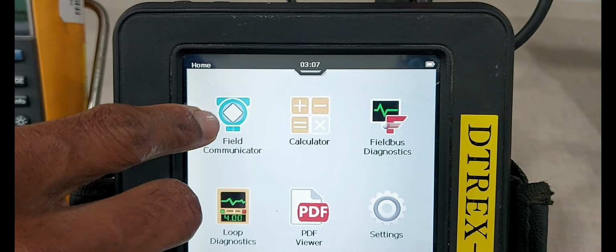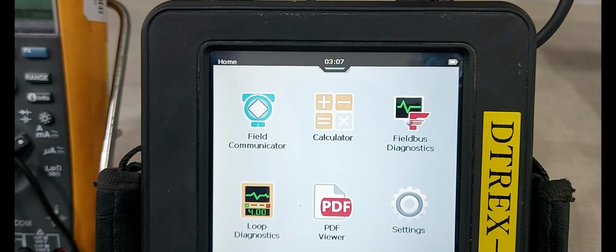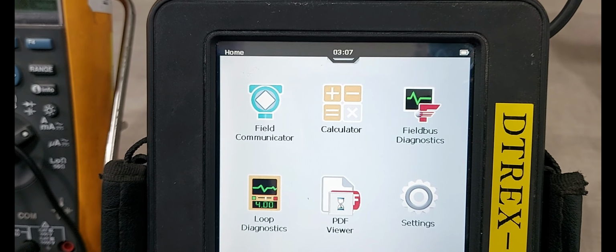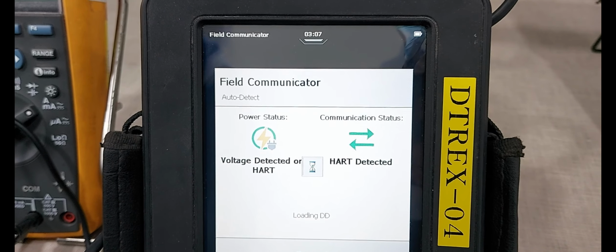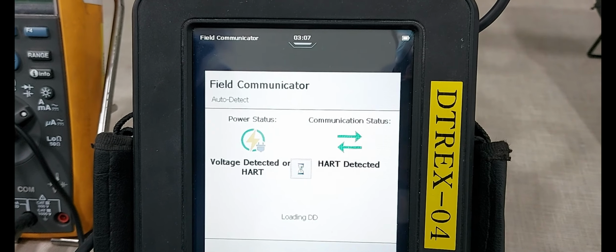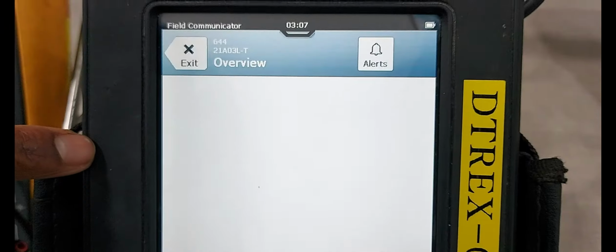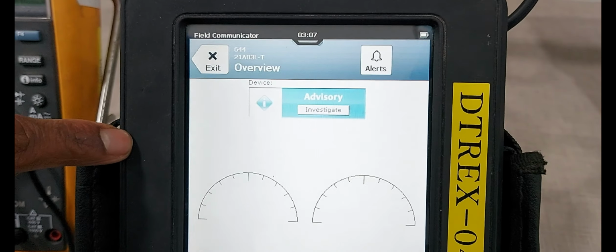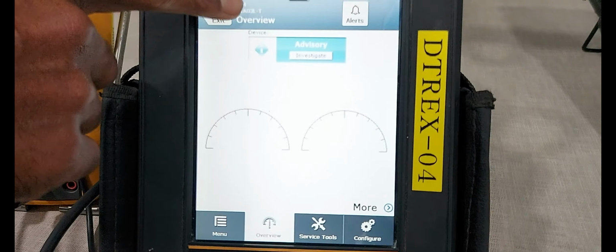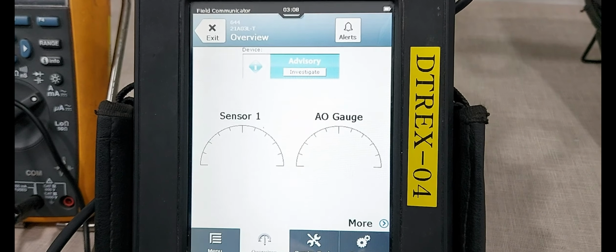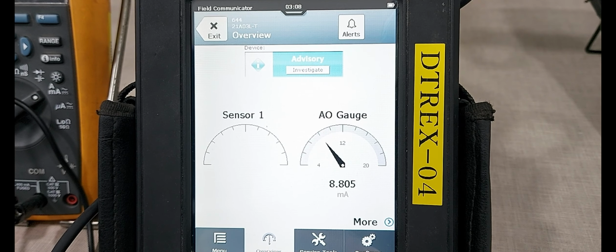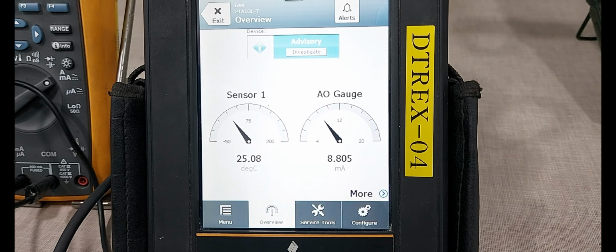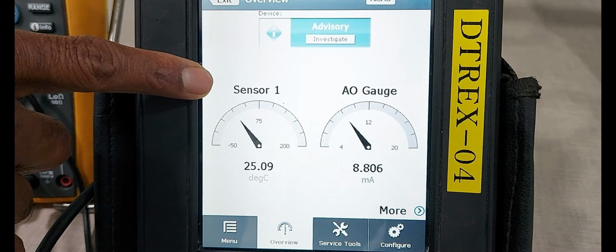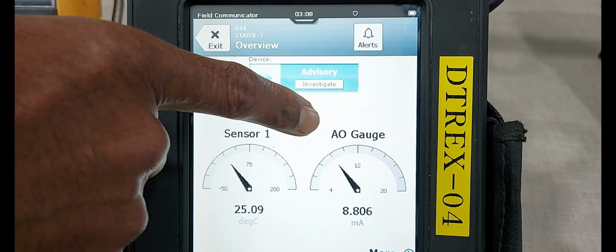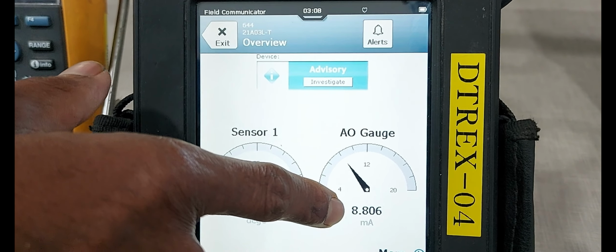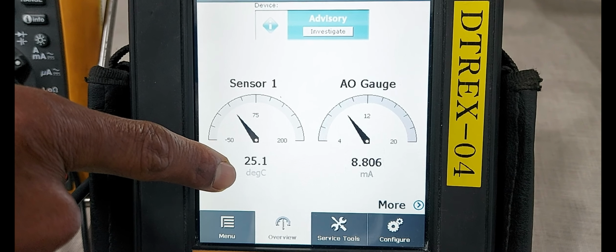Next, select the field communicator menu. Press. Loading DD file. Online menu. This is the overview, service tools and configuration tools. The overview shows the sensor temperature and output value, the analog output gauge value, that is milliamps, and also another temperature.